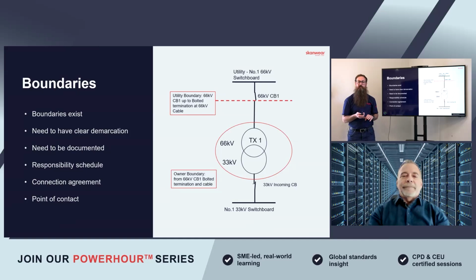That needs to be documented, it needs to be clear. One method would be a connection agreement - it would say where that point is and typically what the size of your connection is. A good thing is to have a responsibility schedule, with clear responsibilities between both parties - who owns what and who maintains what equipment as well.